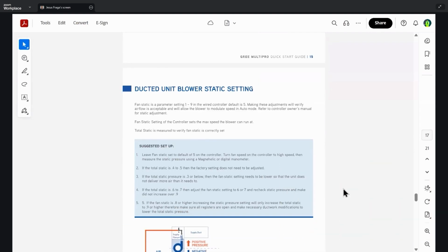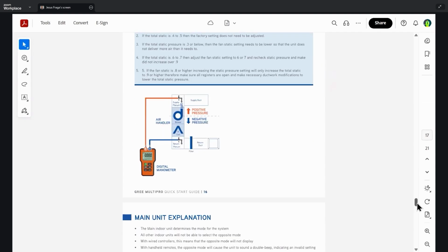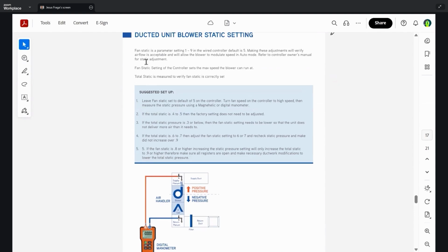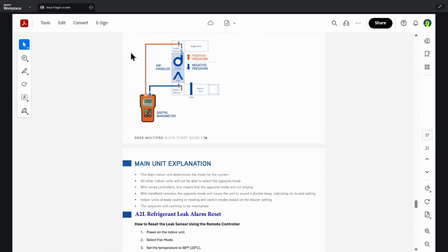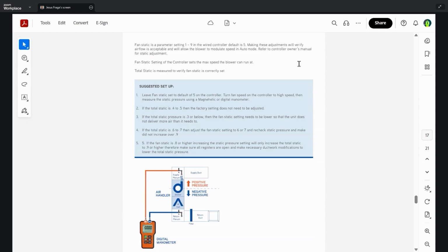So continuing here, the ducted unit static pressure. Similar to the 410A, there are 9 static pressure settings in the wired controller. The units are default for 5, so make sure that you're taking your static pressure across the air handler and adjusting as needed. We recommend that the total static pressure be within 0.4 to 0.5 inches of water column. Anything below or above that will need to be adjusted. So as long as you're within that 0.4 to 0.5, you're good. And here's an illustration on how to actually take the static pressure. As I said, you'll take it across the air handler, so in the return plenum and the supply side, and depending on what value you get is how you'll follow the static pressure settings.